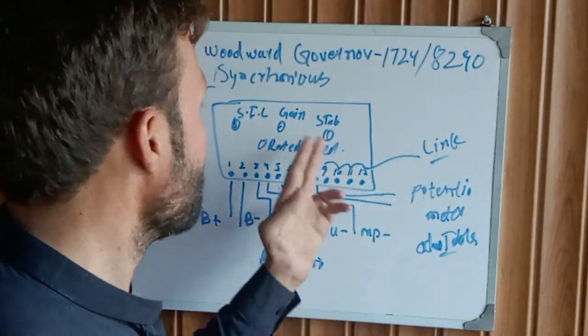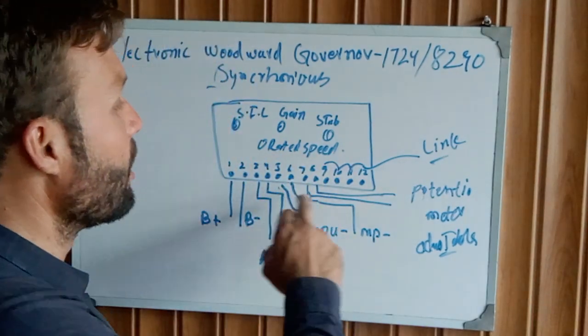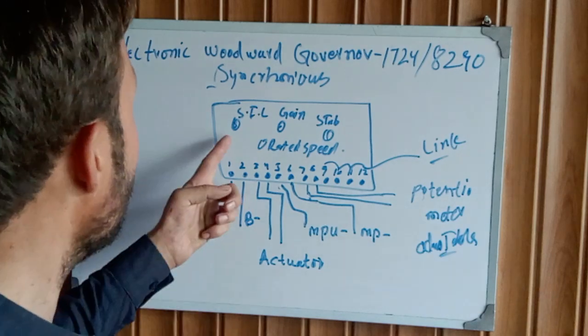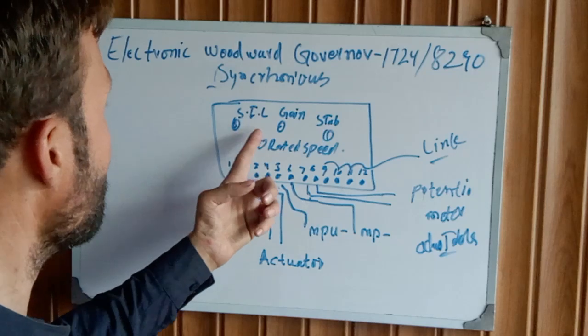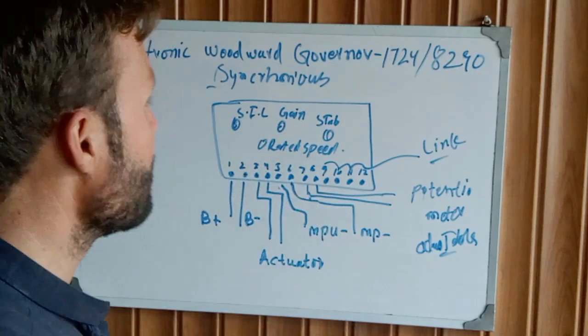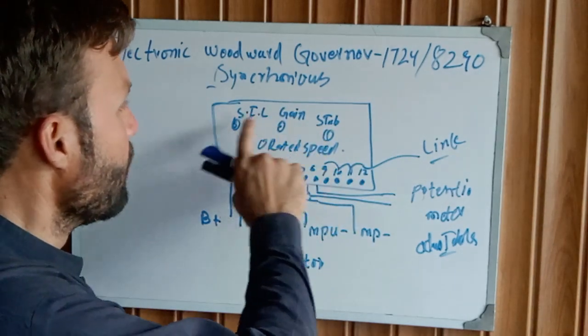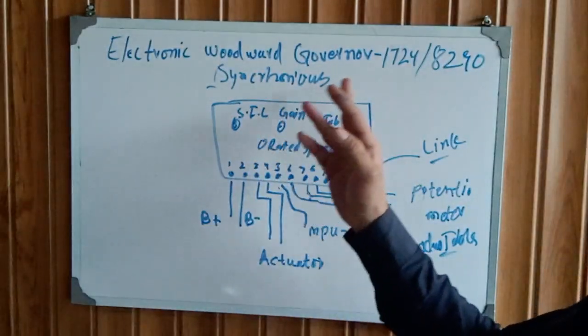This will sense the generator's operating load rating and automatically shut down the other generator. There are some settings - start fail limits, gain, stability, and rated speed. You can set these with a small potentiometer with a screw for your specific settings. This is the complete wiring diagram of the Woodward Governor 8290 model.